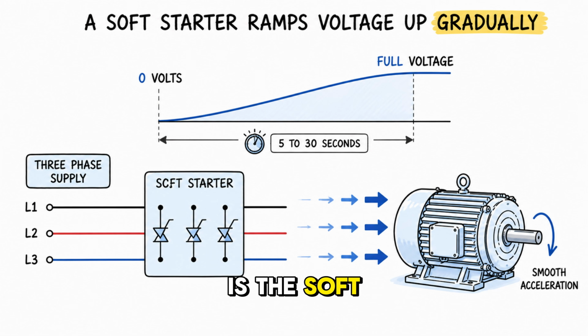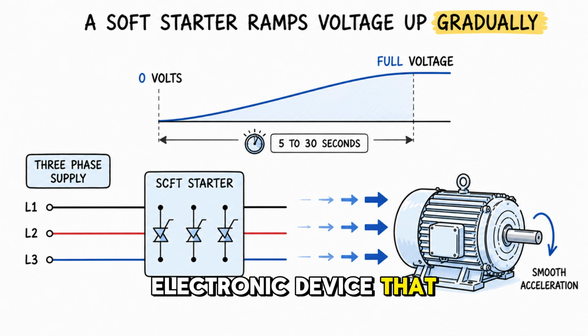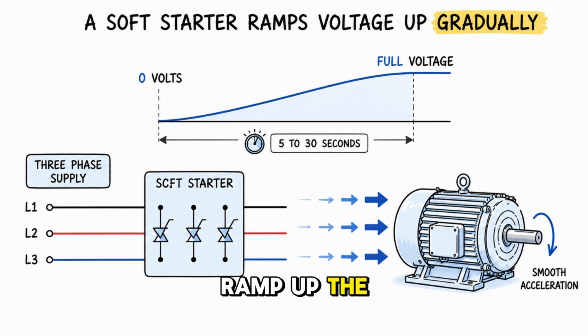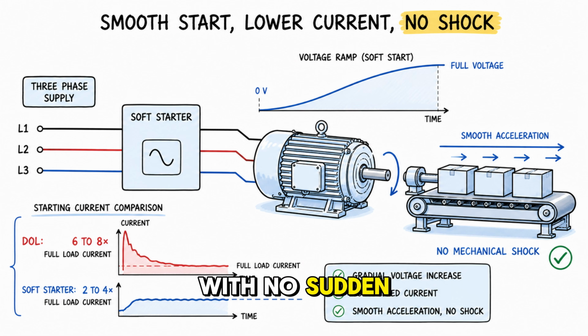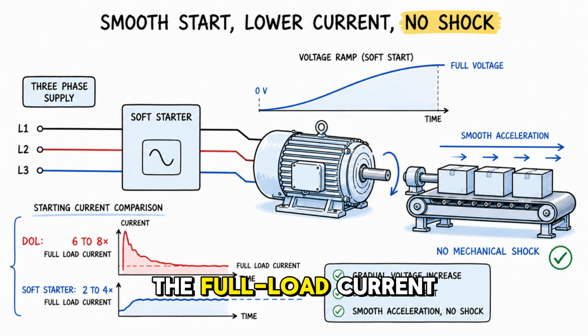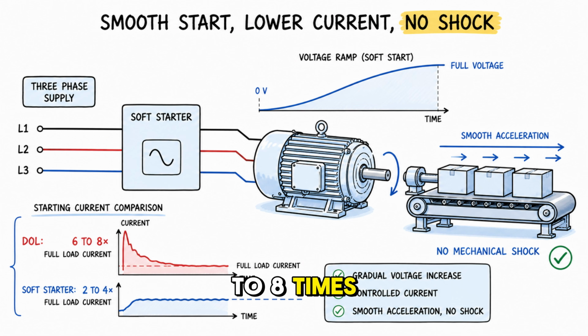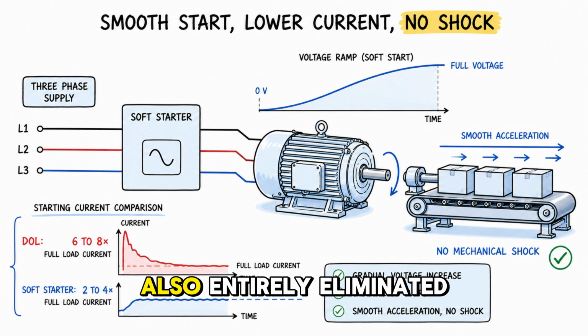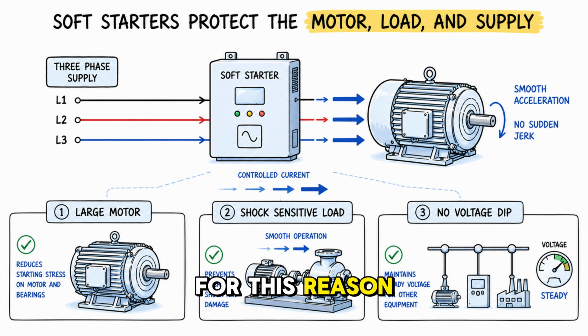The third method is the soft starter. This is an electronic device that uses thyristors to gradually ramp up the voltage applied to the motor from 0 to full voltage over a programmable time period of typically 5 to 30 seconds. The motor accelerates smoothly, with no sudden current surge. The starting current can be limited to just 2 to 4 times the full load current, rather than 6 to 8 times. The mechanical shock to the driven load is also entirely eliminated. For this reason, soft starters are used on large motors, on equipment that is highly sensitive to mechanical shock, and on supply networks where voltage dips are not acceptable.